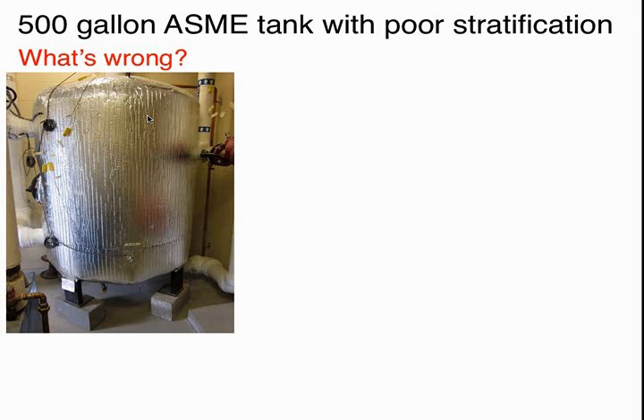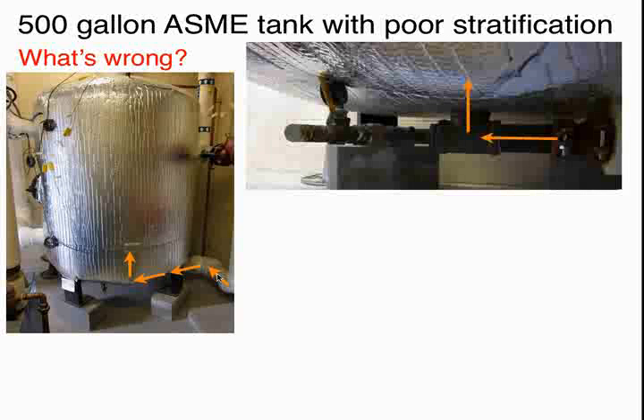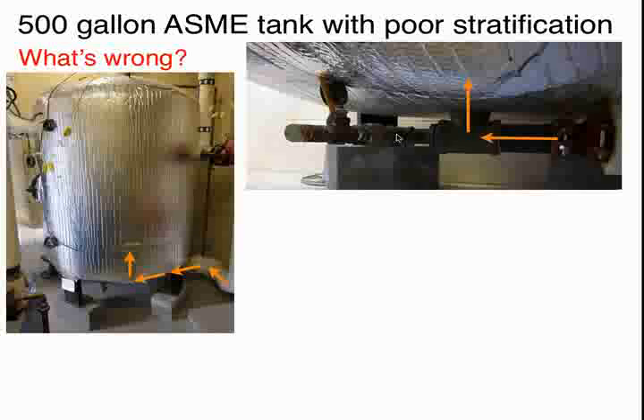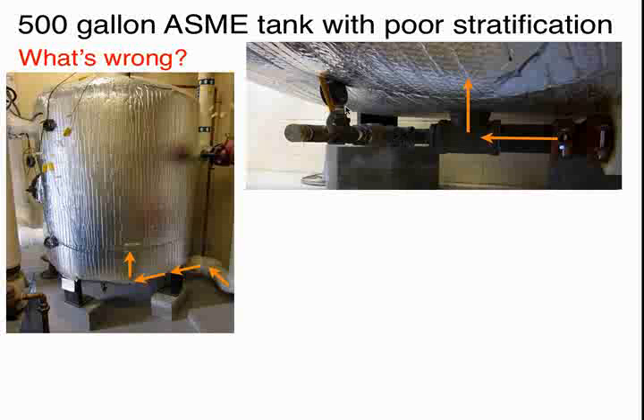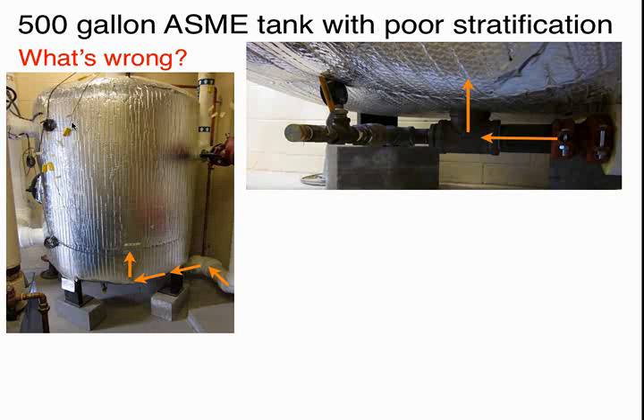Now, here's a tank. This is a 500-gallon ASME pressure-rated tank that's installed as part of a large commercial pellet boiler system we had a chance to look at recently. And you'll see there's various pipes connected to it. It's not obvious, I suppose, in looking at that photo what's wrong, but I'm going to give you a hint. We're going to look at this pipe down here in the lower right-hand corner, and there's the flow path. The flow comes back from the building, and here's another photo that shows the underside of that tank. Just lay down on the floor and look under that tank. We have that 2.5-inch pipe coming in, and this is a T, but the side port of the T ends here. We've got a drain and a pressure gauge. So the flow goes right straight up into the bottom of that tank.